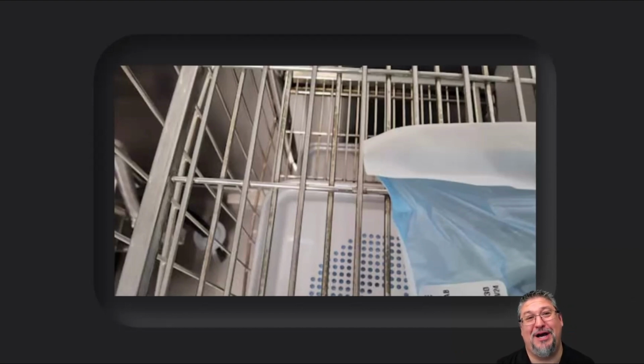This one is a self-seal pouch that's not folded correctly. And my old colleague, Seth Hendy, I love what he used to do, because he used to take these self-seal pouches that were folded incorrectly, and when you blow inside of them, it will blow the pouch up. And guess what? If that air can get in and blow the pouch up, then that's a place where microorganisms can get in too. So your self-seal pouches, this is one surveyors have picked up on. If they're not perfectly sealed across that opening so that there is an airtight barrier, then that's not an acceptable pouch. And surveyors do find those things very quickly and easily on a cursory search. I find them as an auditor as well. When I come into hospitals, I see that in the peel pouching area. So you better be confident that your seals are good when that surveyor walks in the door.